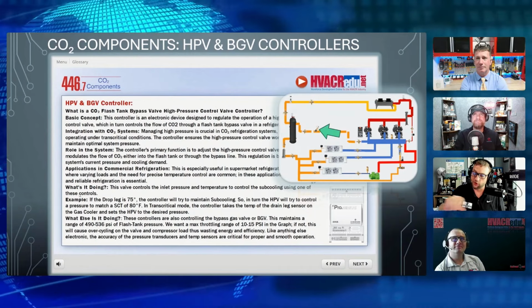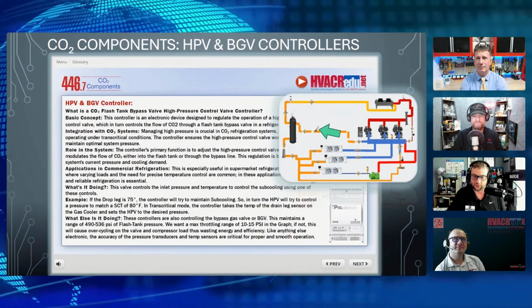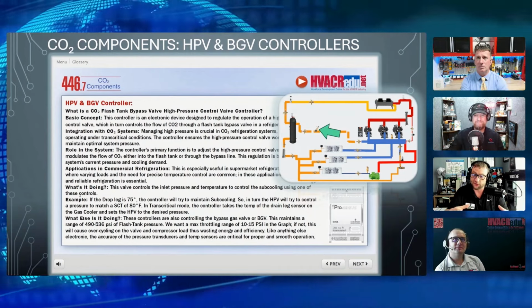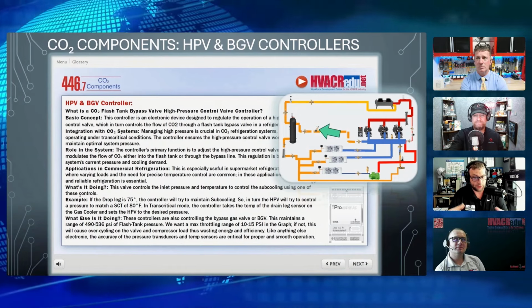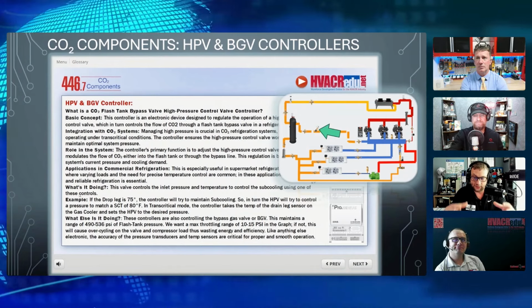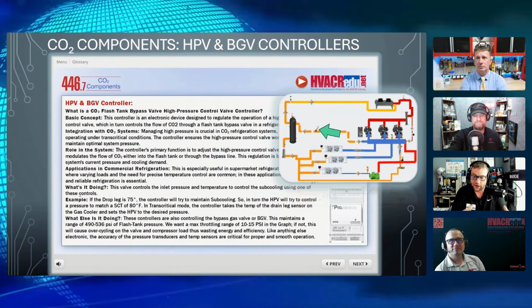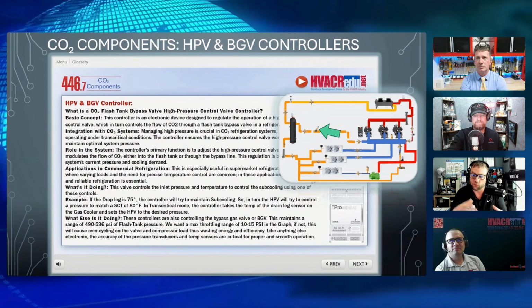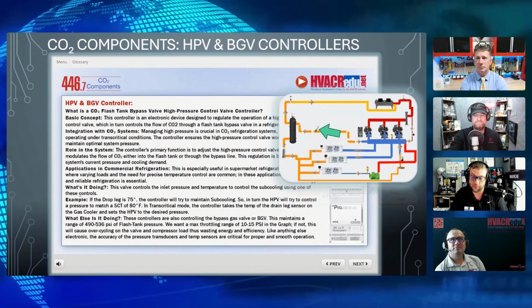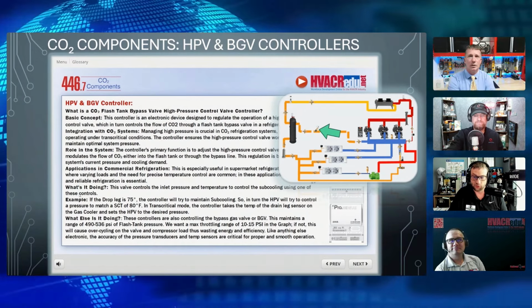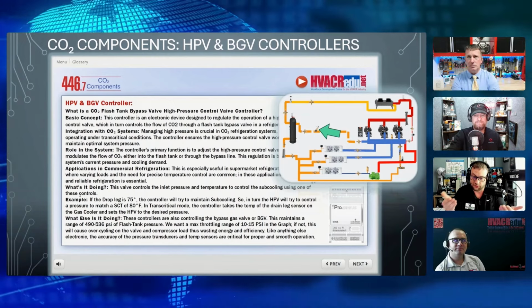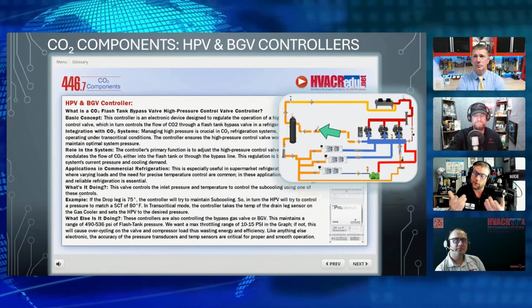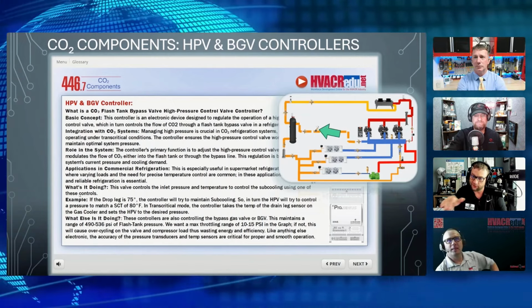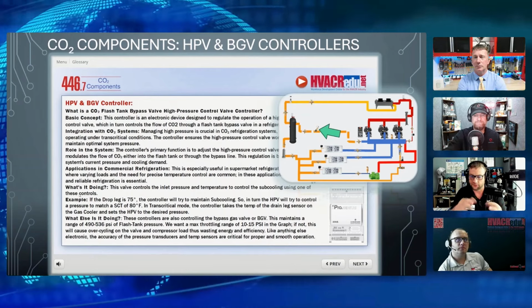So when we drop it down to, let's just say, 35 degrees saturated, that whole vessel, that flash tank, flash receiver, whatever you want to call it, is essentially insulated for that reason, because it is going to get as cold as whatever pressure you're going to get. It's a saturated mixture. At the bottom, you have true blue liquid. And sometimes you'll see in the sight glass a little bit boiling off. If you're right at the top there, you'll see bubbles actually coming on the top because it's basically boiling off that refrigerant.